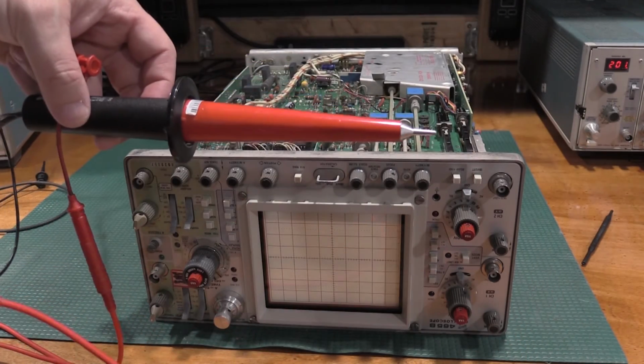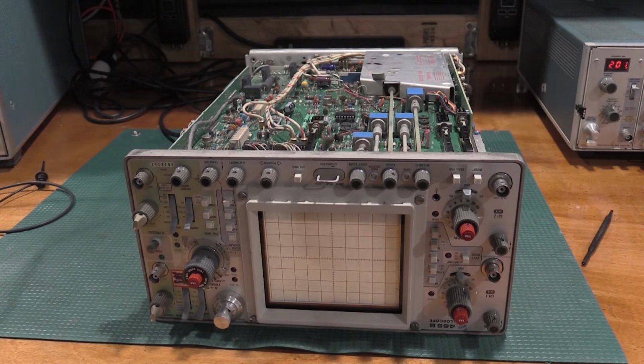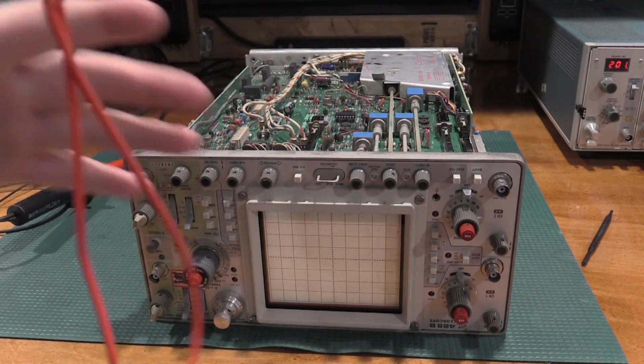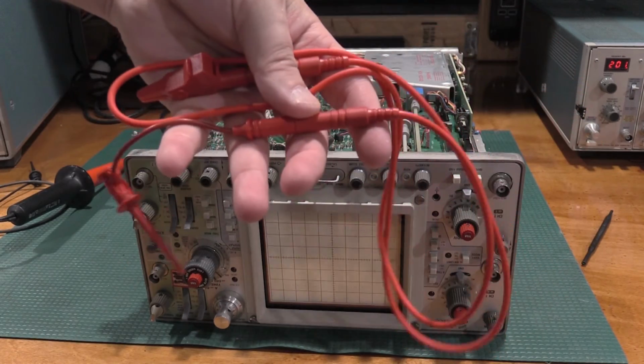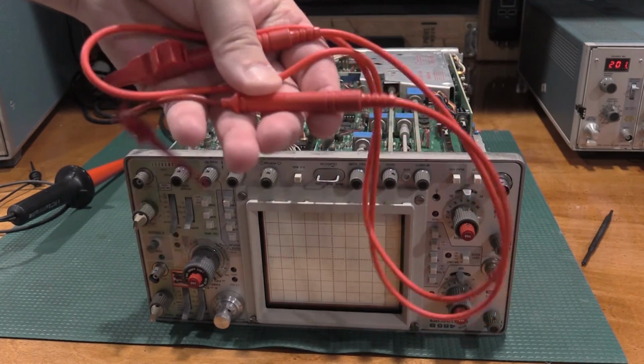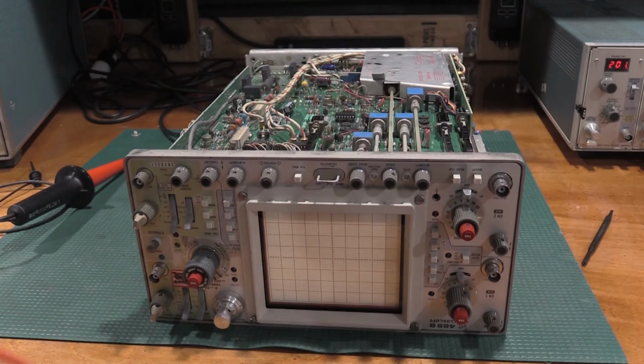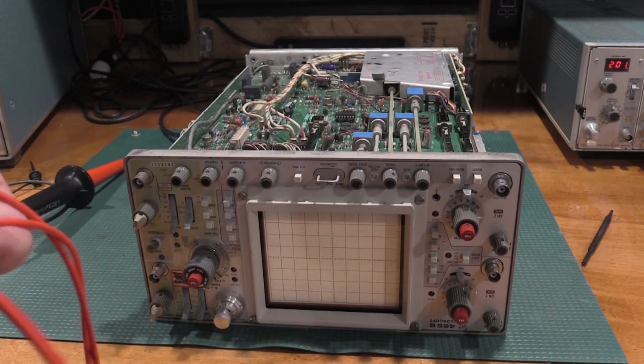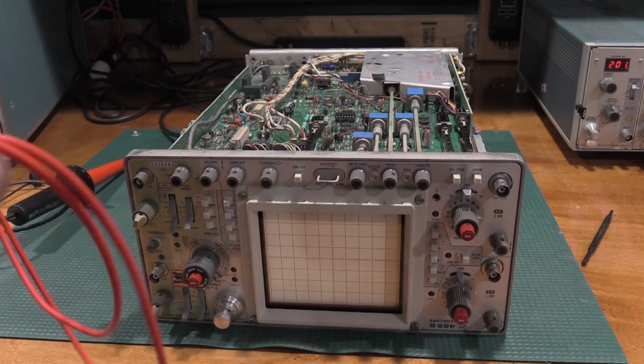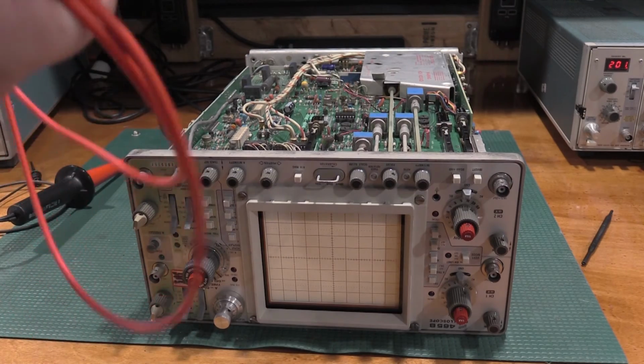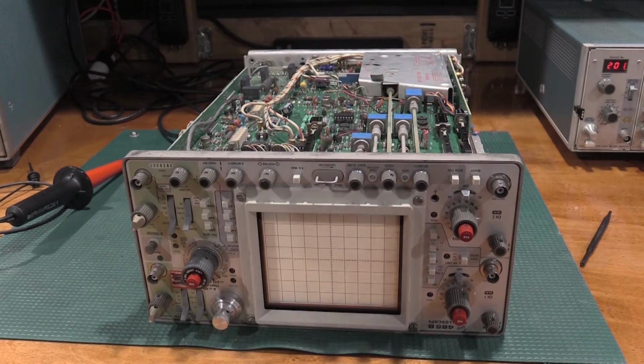Here's the high voltage probe. It's just got a clip in the front end. But I was using this meter wire above its rating. This is only rated for 1,000 volts, so I was definitely getting some leakage current out of that, and I don't want to touch that. Overly cautious? Maybe, but I don't feel like getting zapped today.